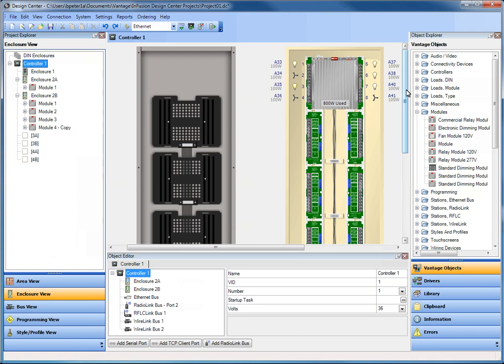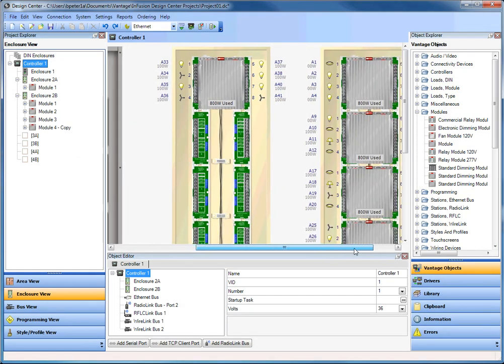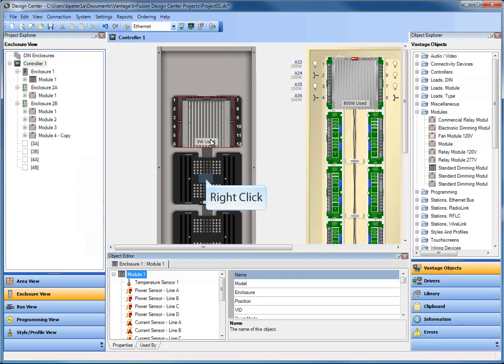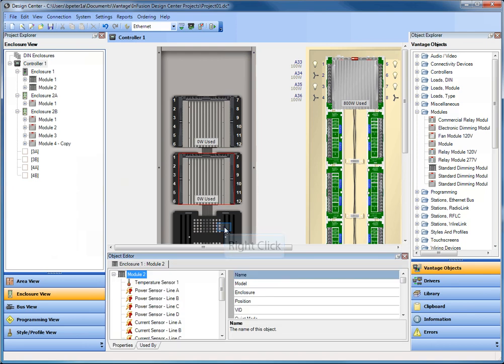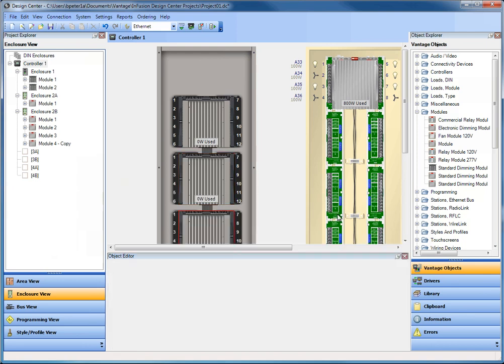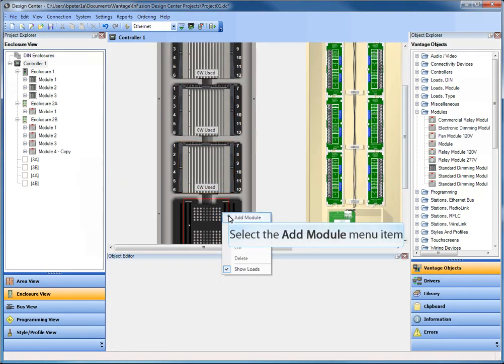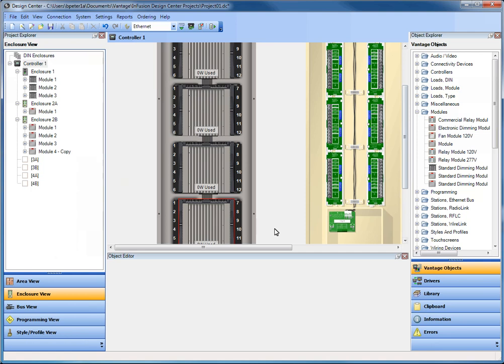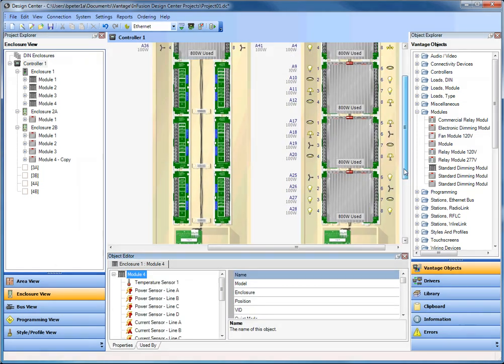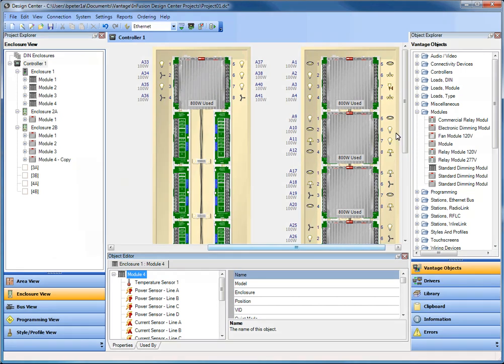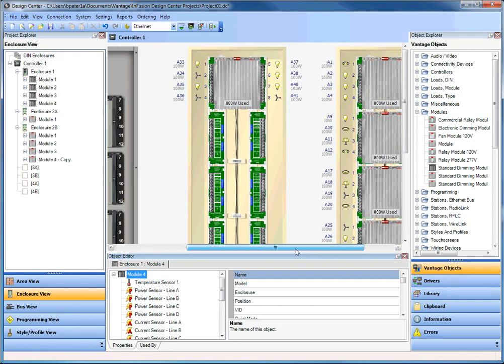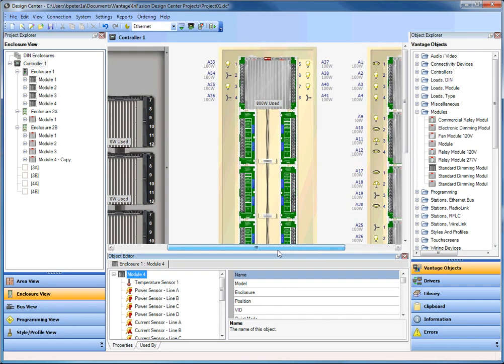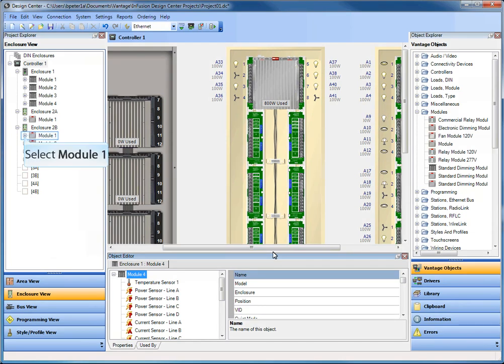What if you needed an older enclosure with the new modules? So what I'm going to do here is I'm going to just undo a couple of those operations real quick and go back to an empty position. Because we don't have the ability to just convert a module per se, I'm going to right click, say add module, right click add module, right click add module. So in this particular case, if you remember, we've added 48 loads, where before in this other enclosure we have 32. So you may be able to save some cost for your customer based on this particular scenario.